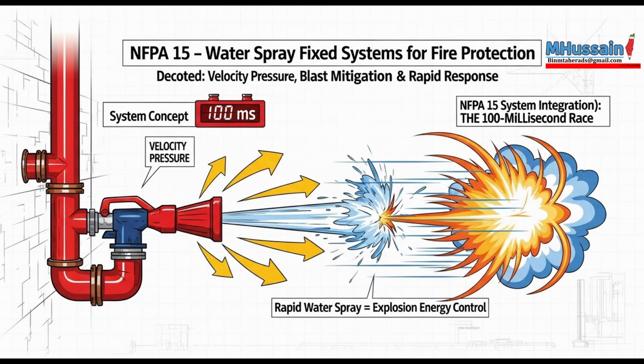It's huge. And because PV depends on velocity, which depends on flow, which depends on the normal pressure PN, which in turn depends on PV, it sounds like a circular calculation, a trial and error loop. It is. Fundamentally, it's an iterative process. You estimate the flow, calculate the velocity and the resulting PV, use that PV to find the PN available at the nozzle, use that PN to recalculate the flow out of the nozzle, and then compare that flow to your initial estimate. Repeat until the estimated flow and calculated flow match within an acceptable tolerance. This level of calculation really necessitates specialized hydraulic software and very careful checking.